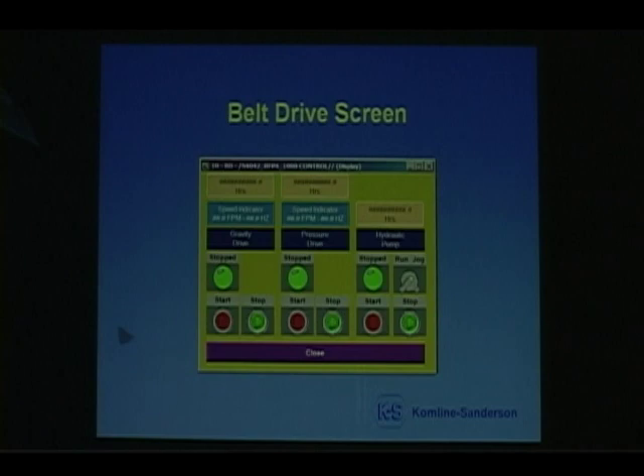This is called the belt drive screen. So when you touch the belt drive picture on the overview screen, the screen will pop up. And on this screen, you've got hour meters and speed indicators. If you touch the speed indicators, another screen will pop up and allow you to change the speed of the belt drive, whichever one you touch, either gravity or pressure. Gravity belt, 0 to 50 feet per minute. Pressure belt, 0 to 20 feet per minute. It reads out in feet per minute and also hertz.